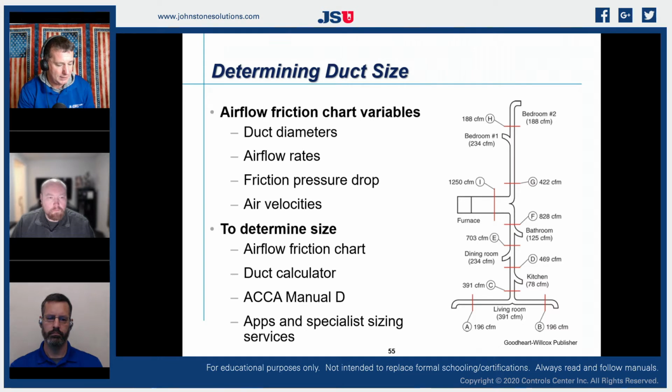I could be a 10 by 20. I could be a 6 by 38. I could be an 8 by 26. Or I could be a 14 by 14. Sounds like a pretty common measurement, doesn't it? So my minimum size is a 14 by 14. A lot of common dimensions, if we had a C-width cabinet, would be a 20 by 20, which is not a problem. That's oversizing. That's going to reduce our restriction on our duct. So we can always go larger with our ductwork. We just can never go smaller. So our minimum size for this would be a 14 by 14 going through the floor.